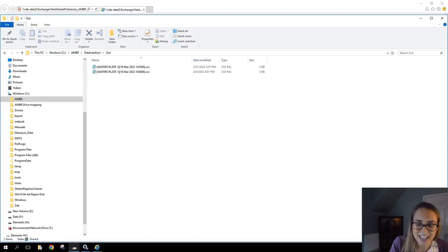Once the study is running, the AMBER 15 takes samples from the vessels automatically and generates a CSV file with the location and the information for each sample. It shares that CSV file in a folder that the BioRecord can access. The user then removes the plate from the AMBER, and they may perform some simple sample preparation steps such as centrifugation. They then put the plate into the BioRecord and are ready to analyse their samples.